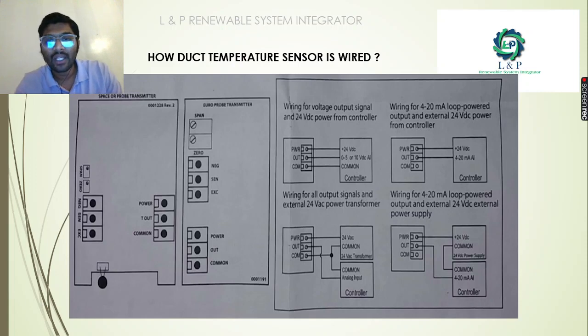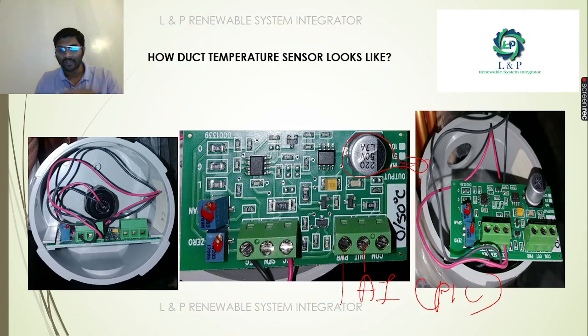As you can see here, if you plan to provide the 0 to 10 volt output, if you want to take the voltage as an output from the sensor, that is going to be your analog input to your devices. If you plan for a three-wire sensor, it means you can connect 24 volt DC to the power, connect the output to the 0 to 10 volt AI of your controller, and then connect the common here. So this is a three-wire wiring.